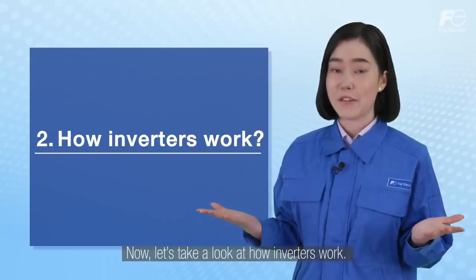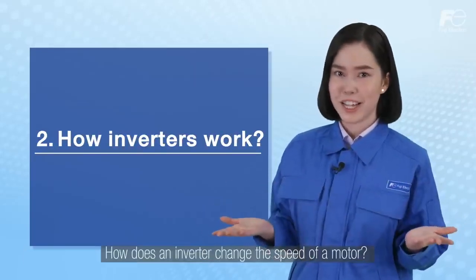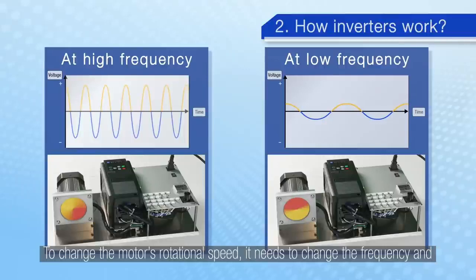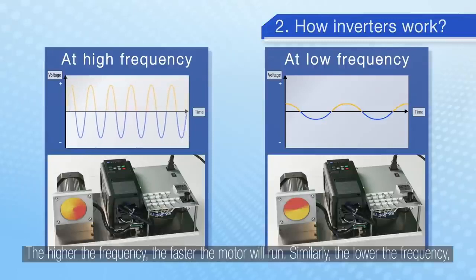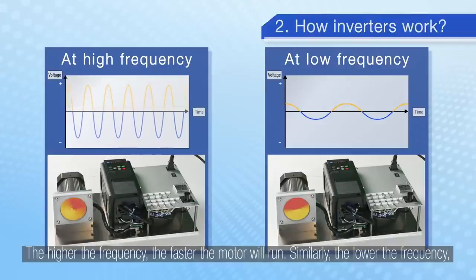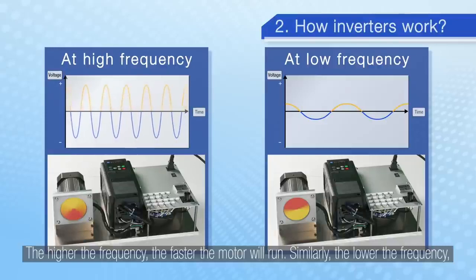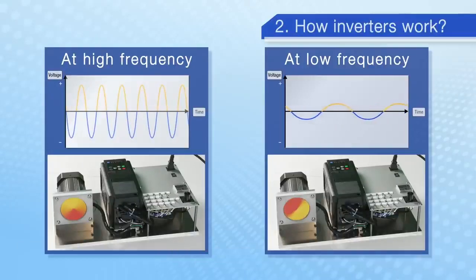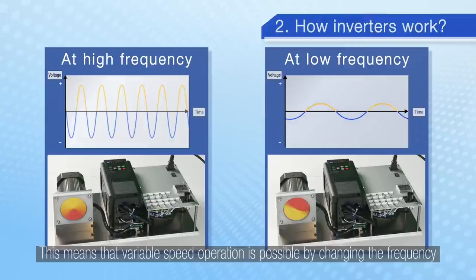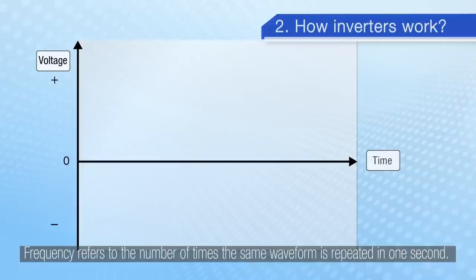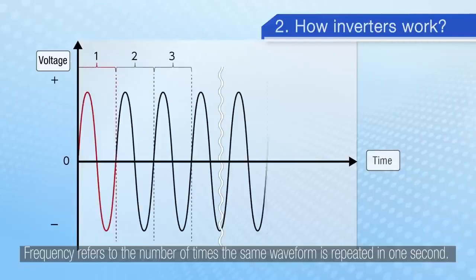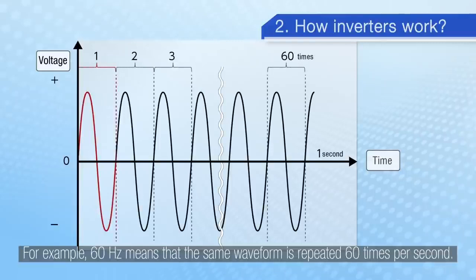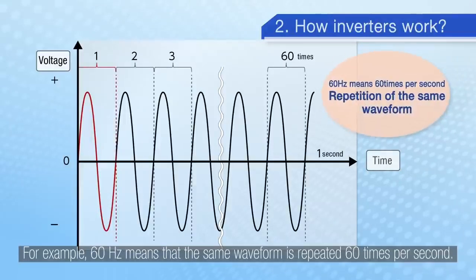Now, let's take a look at how inverters work. How does an inverter change the speed of a motor? To change the motor's rotational speed, it needs to change the frequency and voltage applied to the motor. The higher the frequency, the faster the motor will run. Similarly, the lower the frequency, the slower the motor will run. This means that variable speed operation is possible by changing the frequency and voltage of the inverter. Frequency refers to the number of times the same waveform is repeated in 1 second. For example, 60 Hz means that the same waveform is repeated 60 times per second.